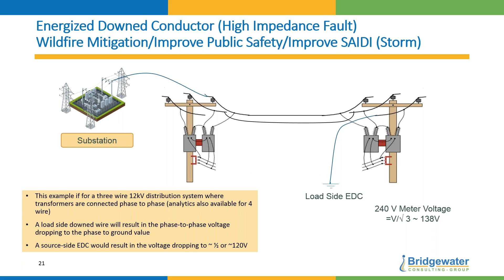This was one example that we showed at Distributech, which I did jointly with Southern California Edison. This was at a location, and it was an interesting one where the truck went out and repaired a blown tap, and then the truck left. Then in the morning, somebody came out and said, hey, there's a sparking wire in my backyard. So for 10 hours, that wire was down. And you can look at the voltages, 247, 149, 140. Ooh, that's your load side voltage. And it was repaired, but it was a wake-up call.